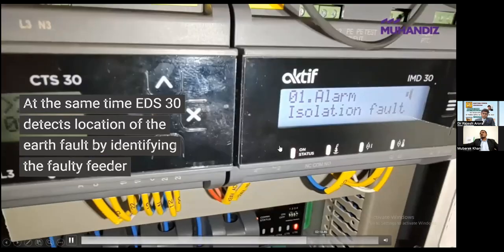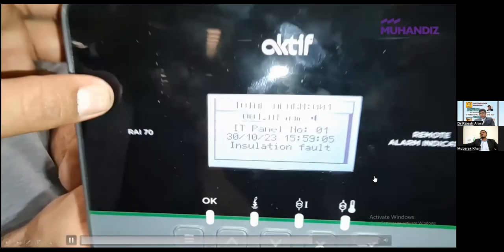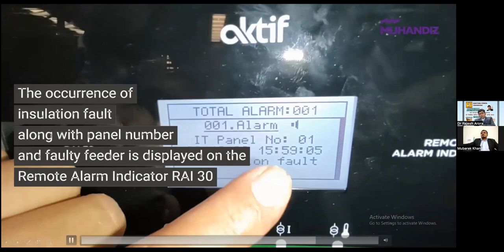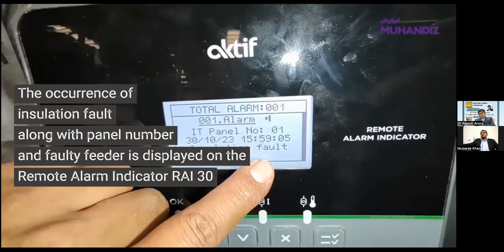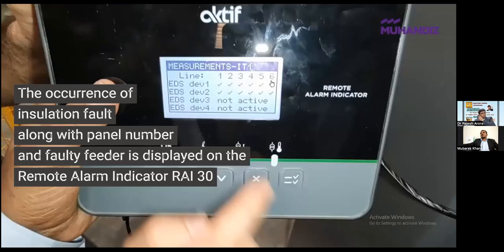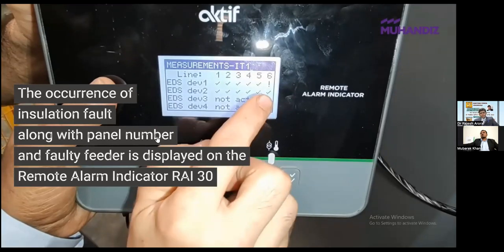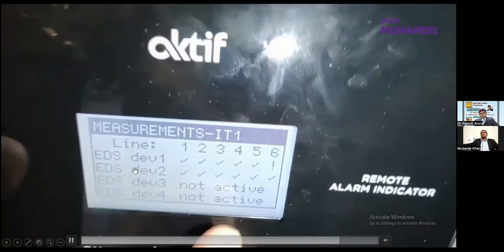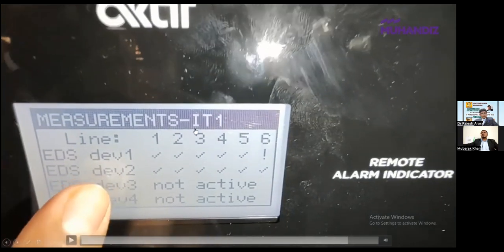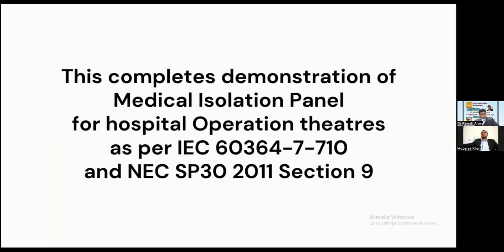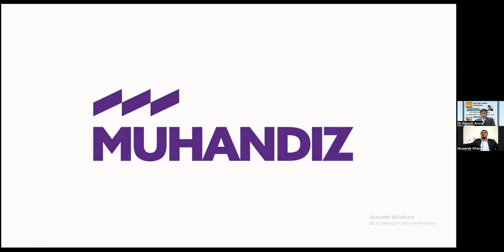Now the same data is displayed on a remote panel. You can see. As you can see, feeder number 6 of IT1 is faulty. It is showing on this one. Okay. And because this displays the indication of various IT systems, it is showing IT1, the first isolation panel, feeder 6 is having a problem. Okay. That is the end of the demonstration for the medical isolation panel for hospital operation theatre as per IEC 60364-7-710 and NEC SP30 2011. Okay.